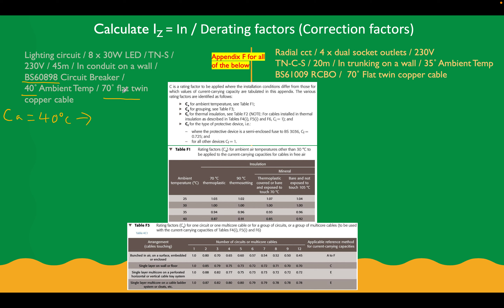So CA on this circuit is equal to 40 degrees Celsius. We've got 70 degree flat twin copper thermoplastic cable and a 60898 breaker. Looking at the ambient temperature table at 40 degrees for a 70 degree thermoplastic cable, our correction factor CA is going to be 0.87. It's as simple as that — just navigate the table and get our correction factor.